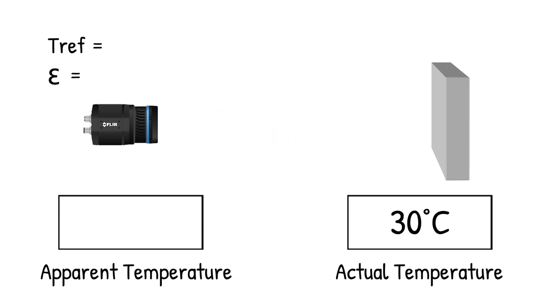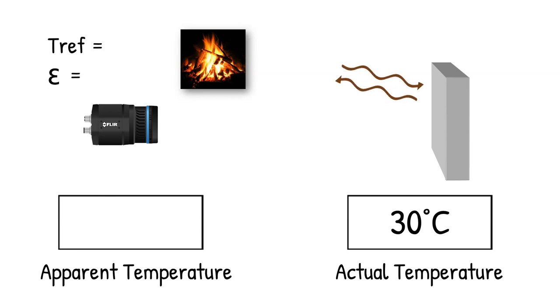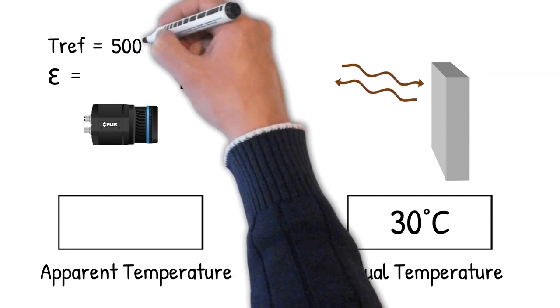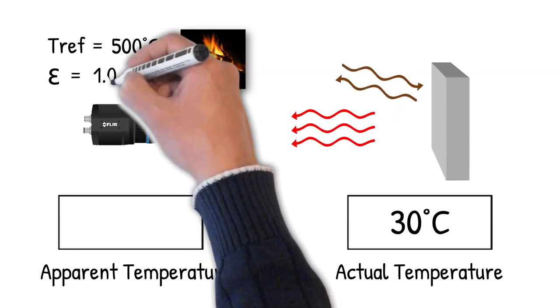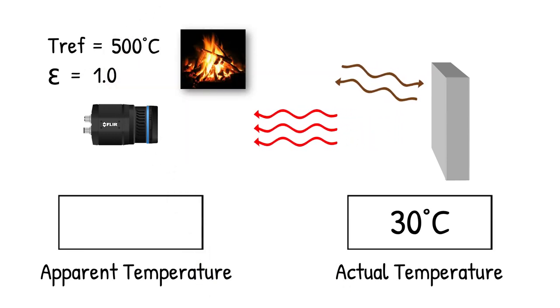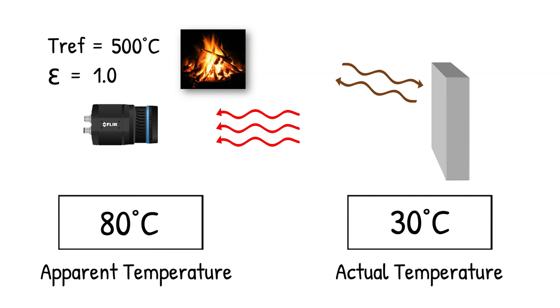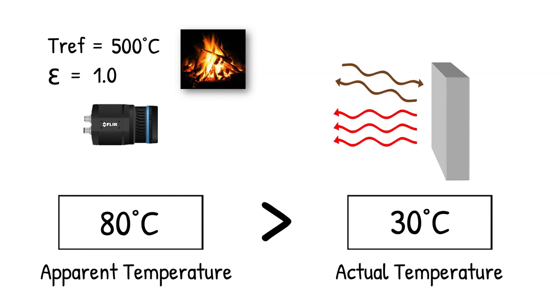If the reflected energy source is a large fire with a temperature of 500 degrees C, and the camera emissivity setting is set to 1, the infrared camera will report an apparent temperature higher than the actual target temperature. The 500 degree reflected radiation will add to the 30 degree emitted radiation from the target.